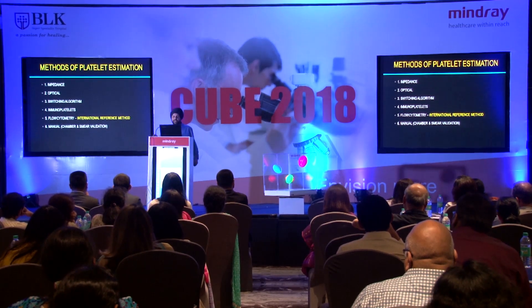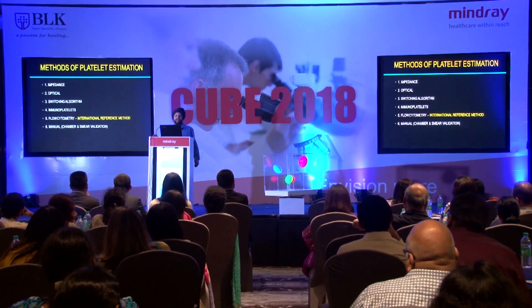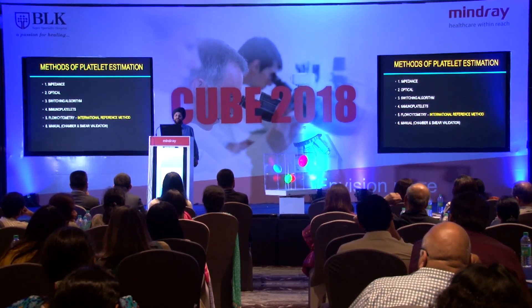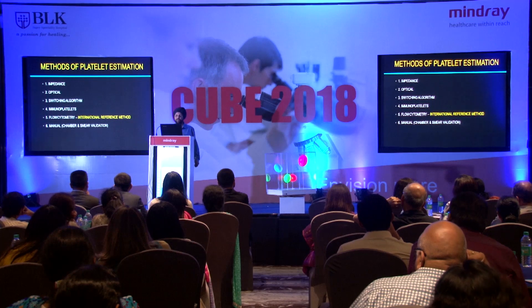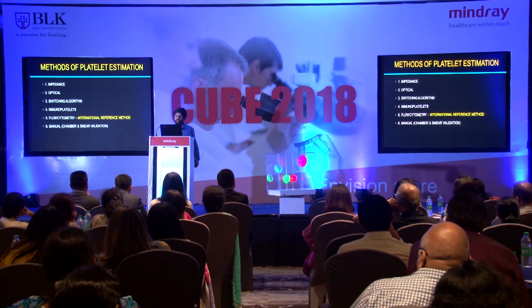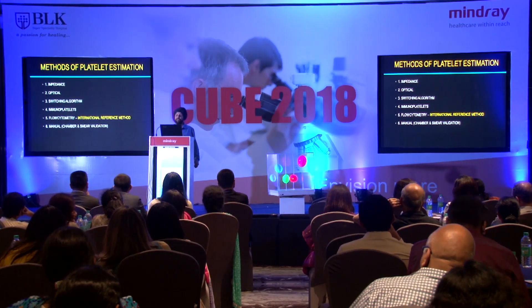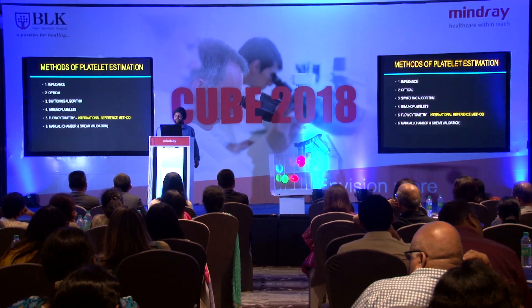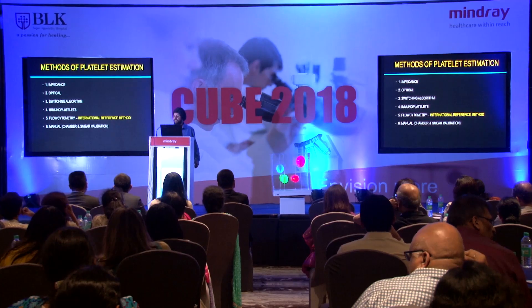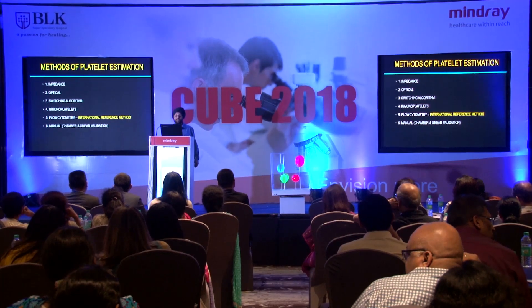These days, most analyzers have a switching algorithm where you can do both impedance and optical based counts. The machine will decide for you under which condition which count is better, and you can use the switching algorithm when you do both counts.